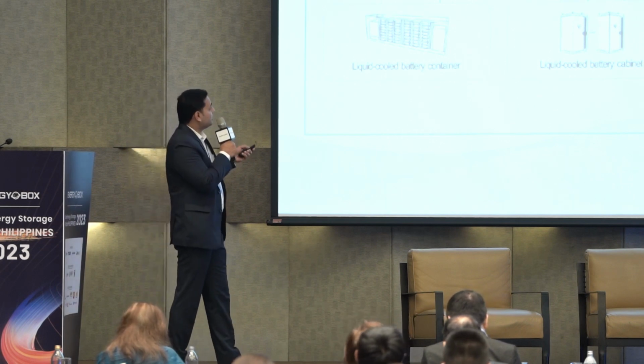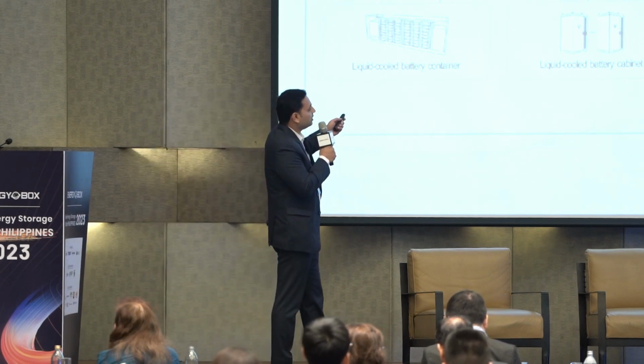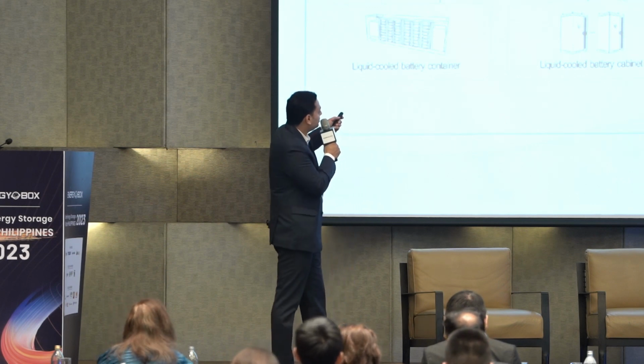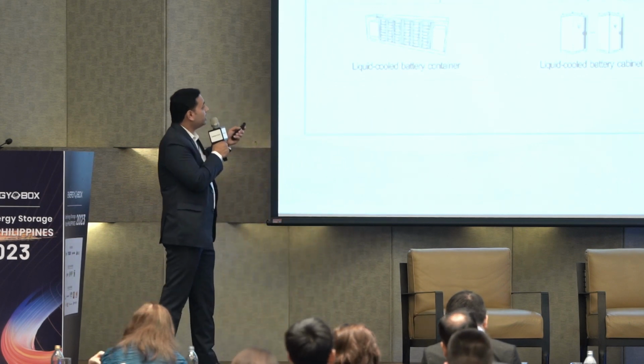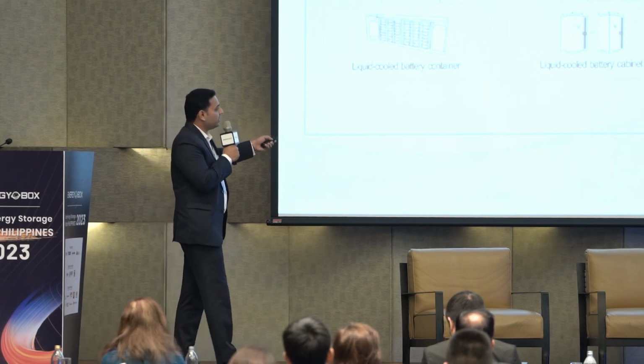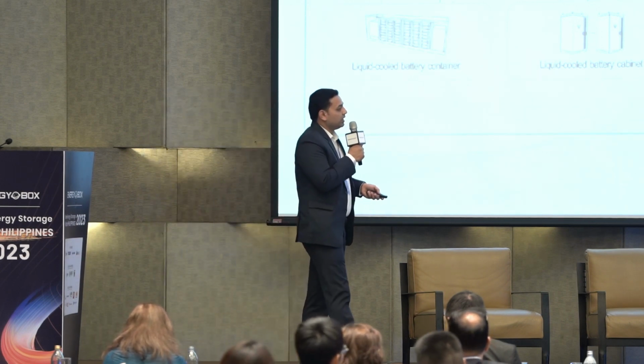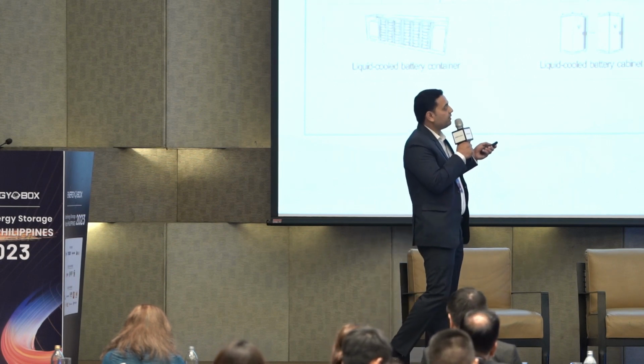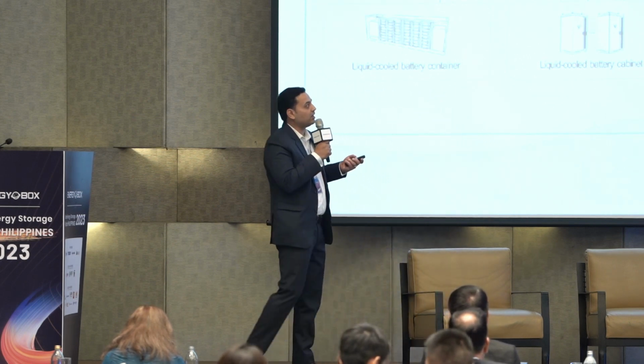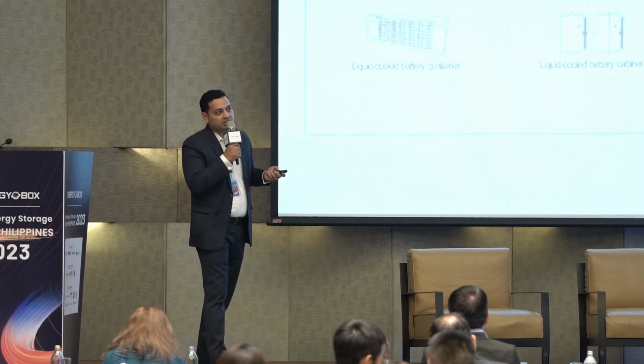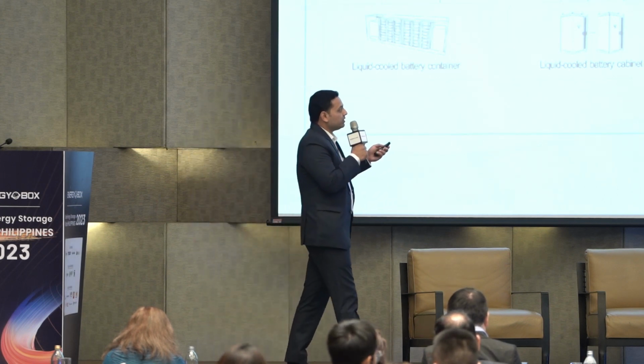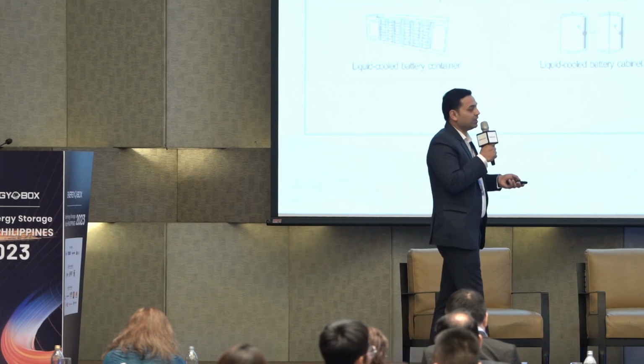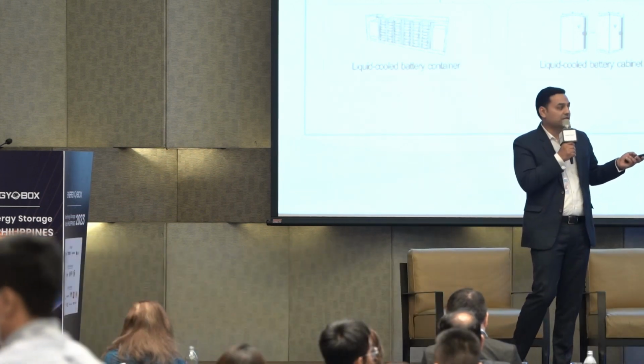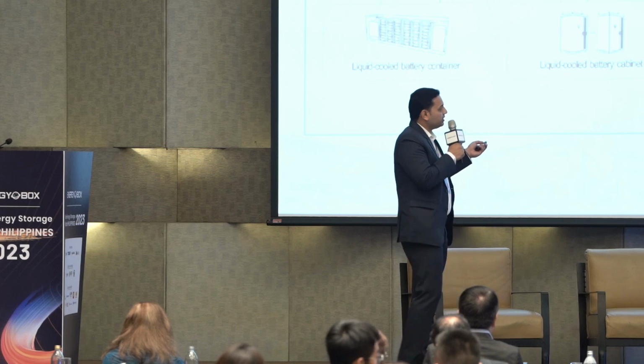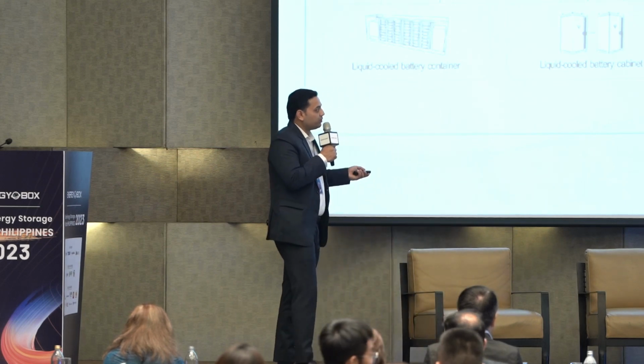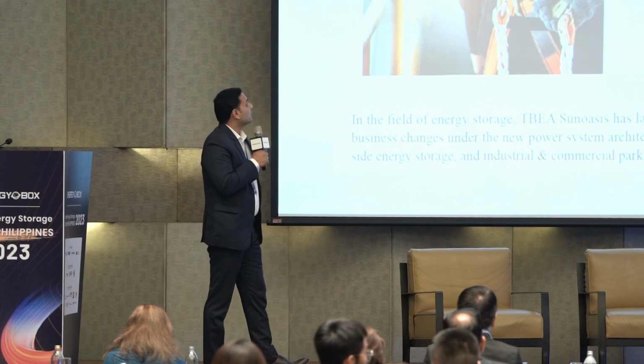Liquid cooling energy storage system. We come up with a different solution for storage, where we have string integrated PCS, liquid cooled battery container, liquid cooled battery cabinet. The advantage of this solution is it will have a cluster level management, which will increase the consistency and the battery discharge capacity by 7%. The temperature difference of this liquid cooling system is consistent, and the battery life is expected to increase by 20%. Again, it's a modular design solution, which is very convenient for operation and maintenance.